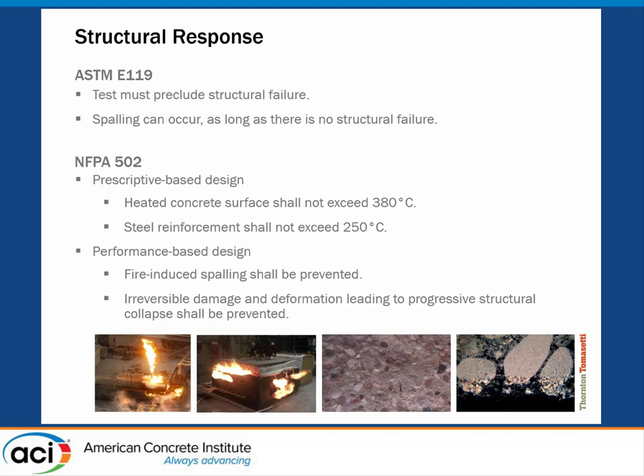From a structural response standpoint, ASTM E119 is the governing fire time-temperature curve for our standards, and spalling can occur — it really only cares about structural failure. In order to have a two-hour fire resistance rating, you need to withstand temperature limits on the unexposed surface and not fail; it doesn't care about spalling as long as those other requirements are met. NFPA 502 does have some information: the prescriptive-based design part has temperature limits for heated concrete surface and steel reinforcement. The performance-based portion states fire-induced spalling shall be prevented — a blanket statement that's almost too strict, since it's very hard to completely prevent concrete spalling.